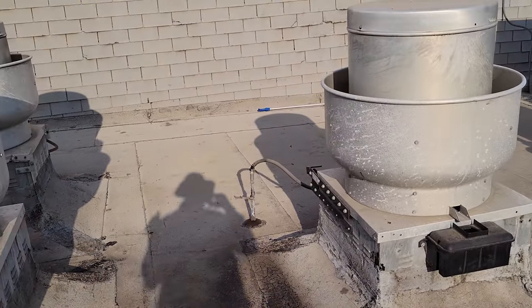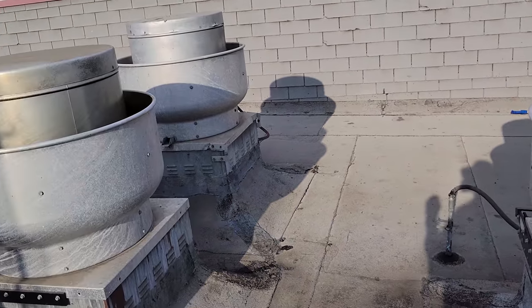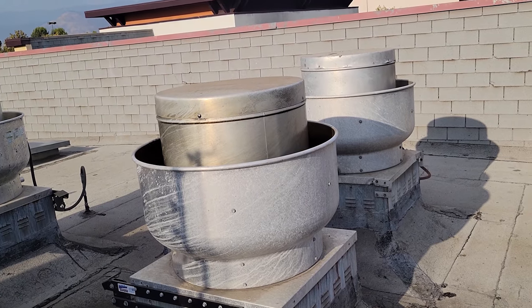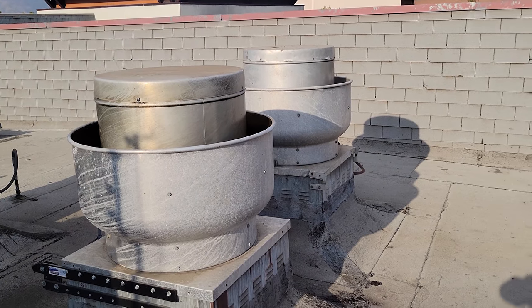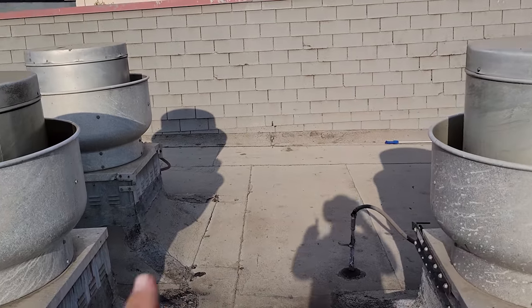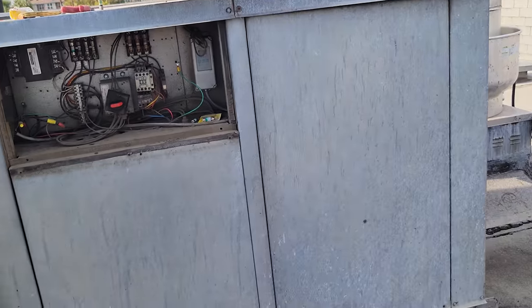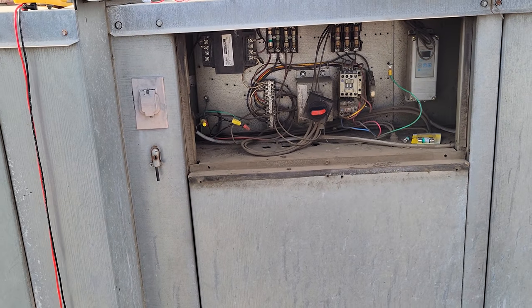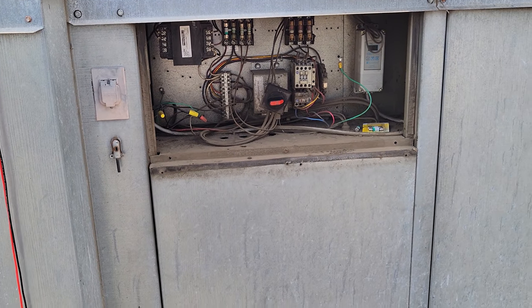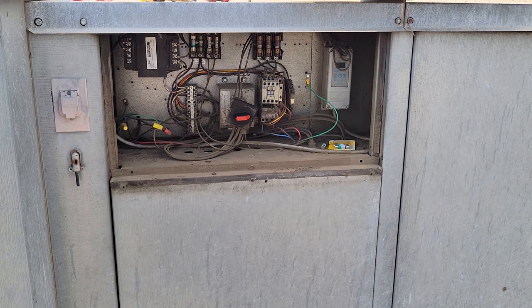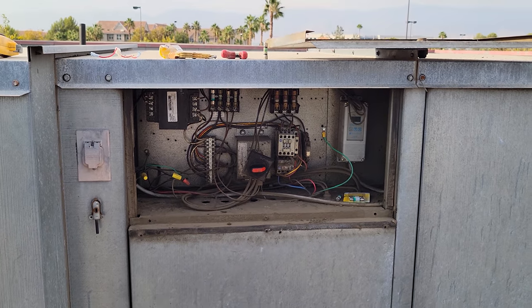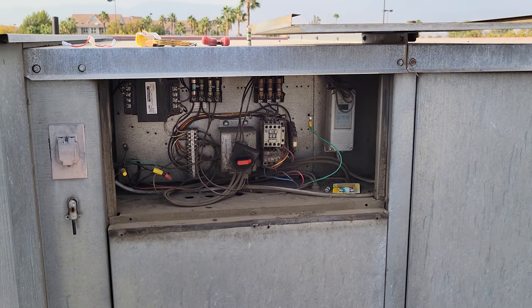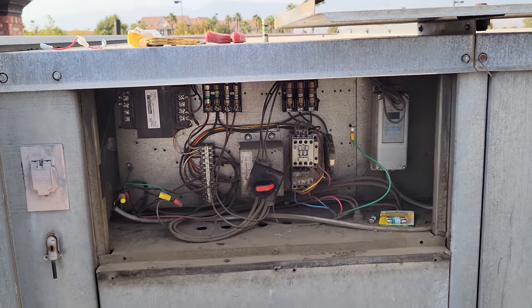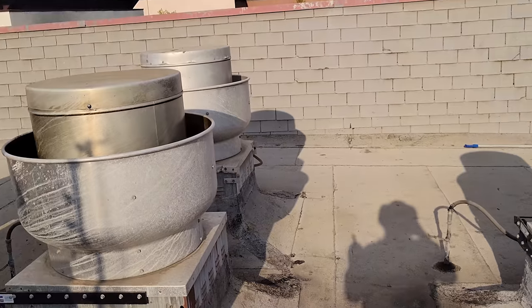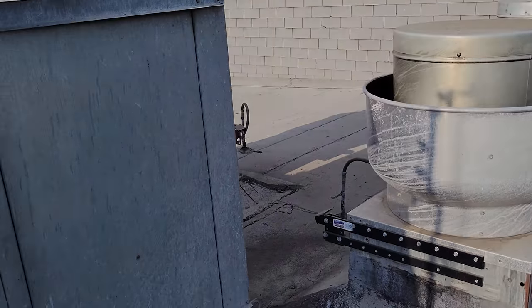Now, I talked about a shunt breaker. Sometimes they will have like an interlink. If something happens, it'll trip a breaker. Like if the Ansul system goes off or something like that, and it can shut down all the cooking appliances, but it typically doesn't shut off the exhaust fans. So that's why I was kind of blown away. Yeah, that's what they typically do in a fire situation. If the Ansul or fire suppression system was to go off, it triggers a micro switch that will trip a breaker, because it's supposed to shut down any fuel sources for the building. But when that happens, they typically will shut down the makeup air because that fuels the fire, and then they turn on the exhaust fan so that it can suck the air out of the building and suffocate the fire.